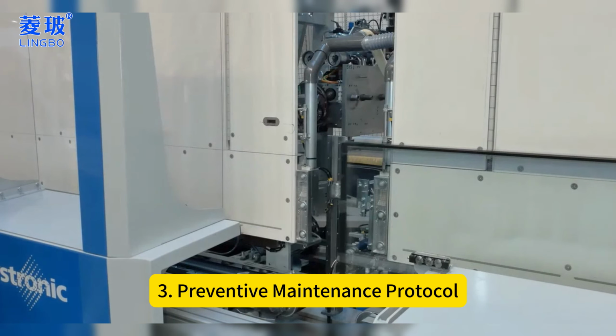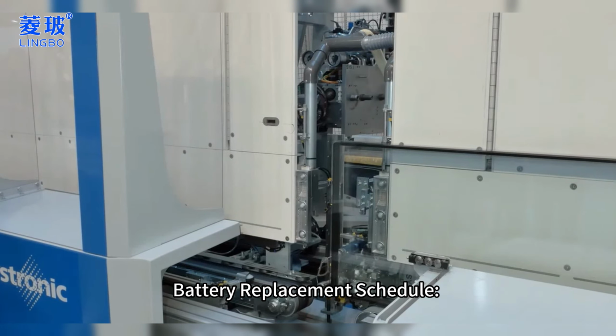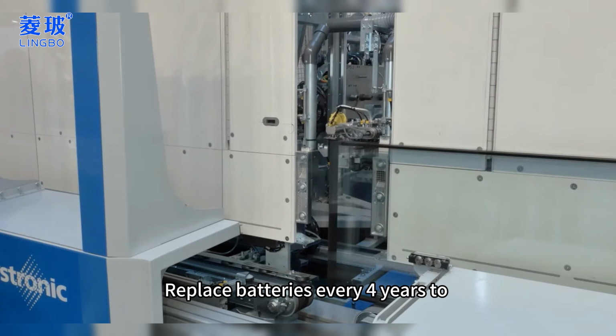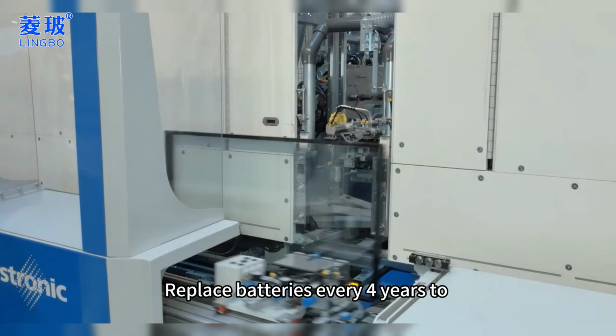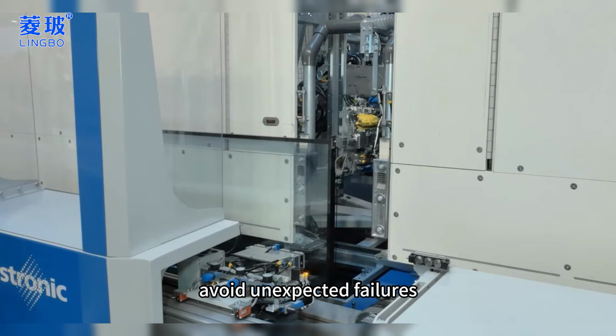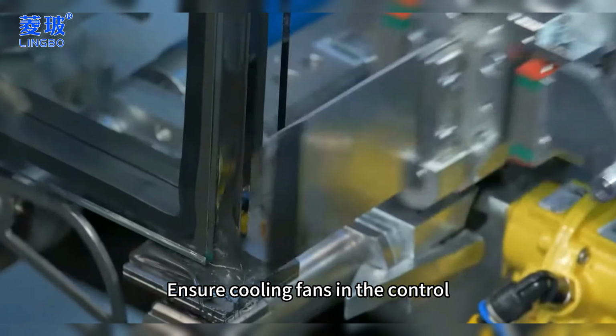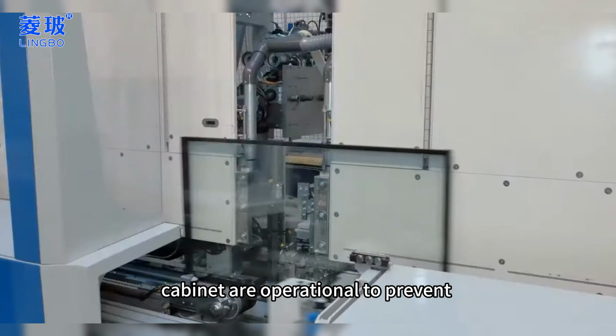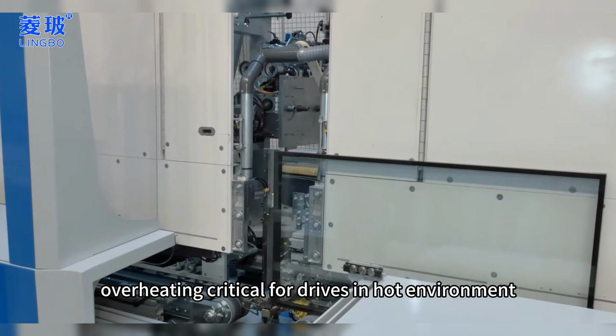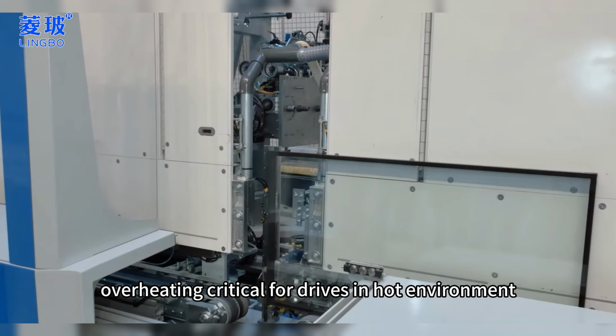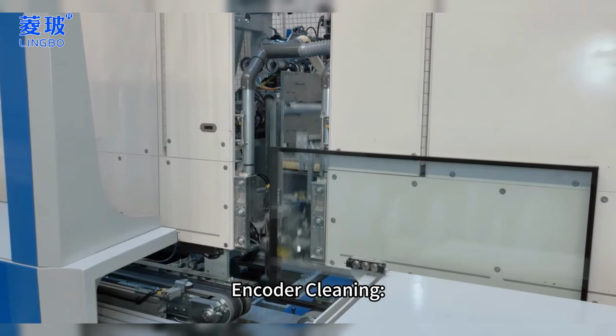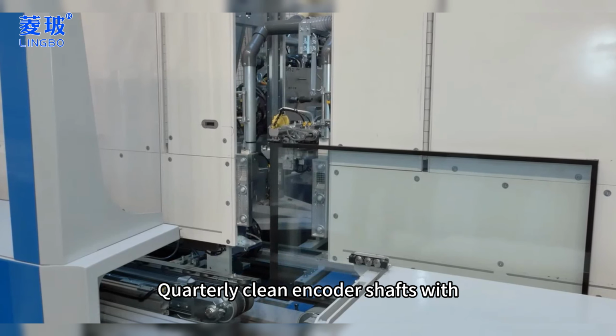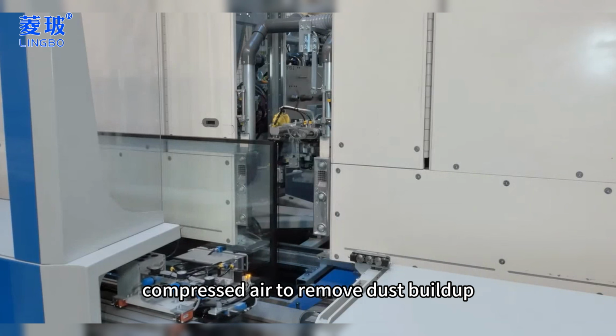Section 3. Preventive Maintenance Protocol. Battery Replacement Schedule. Replace batteries every 4 years to avoid unexpected failures. Drive cooling. Ensure cooling fans in the control cabinet are operational to prevent overheating, critical for drives in hot environments. Encoder cleaning. Quarterly clean encoder shafts with compressed air to remove dust buildup.